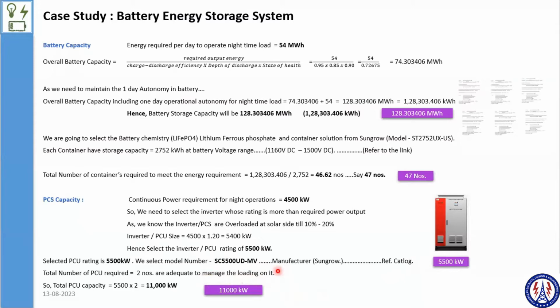Yeah. The point is you're investing more on the battery, right? And you're putting huge funds on it. And if you look at the cost comparison, the PCS cost is very low as compared to your entire battery cost. Let's say the selected PCS has some fault. At least your other PCS should activate, or even manage the entire load for some time, right? And the second approach is, you are thinking only of discharging mode, correct?